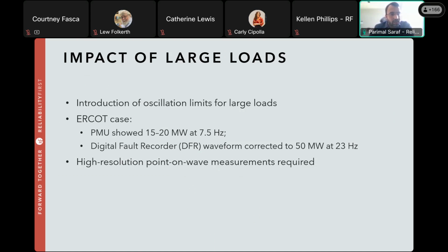And ERCOT also observed in a case study, or an event analysis, that PMUs installed in the ERCOT or Texas footprint showed a forced oscillation being induced into the system, basically with a variation of 15 to 20 megawatts at 7.5 hertz. But under further investigation using a digital fault recorder, it was observed that the actual oscillation was sized at 50 megawatt amplitude at 23 hertz frequency. This was also discussed in one of the recently published NERC Large Load Working Group white papers.